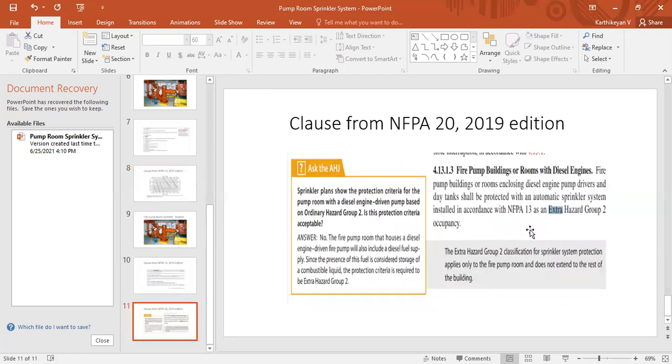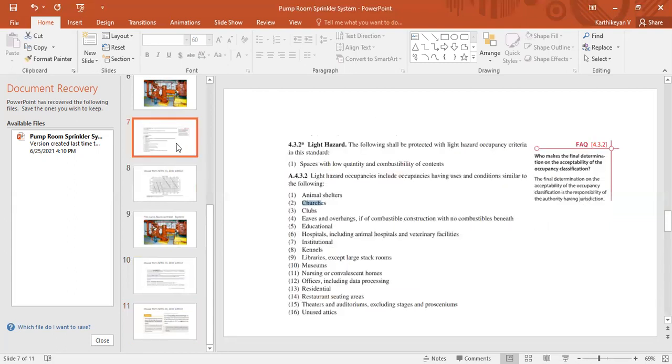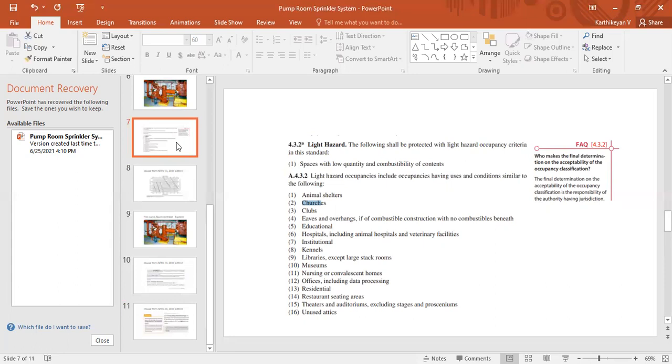As of my knowledge, actually what NFPA 13 tried to convey is, if our project contained only electrical pump, then we can go with 10.2 lpm per square meter. If our project contained with diesel pump with diesel day tank, then we have to go with extra hazard group two. Whatever consideration is higher we need to select that one. This is the correct one because in realistic scenario we cannot see any project without diesel pump with diesel day tank. So here I'm clearly stating fire pump room hazard will be extra hazard group two.